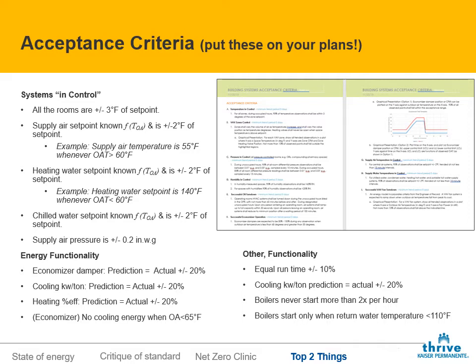And it turns out, what we've learned here, I guess, is that acceptance criteria fall into two categories. The first category of acceptance criteria is that you have your systems in control, right? All your rooms are plus or minus 3 degrees at the set point. Your supply air is plus or minus 2 on your supply air temperatures and your supply water temperatures, right? The pressures should all be within a margin of error that's within expectations. That's the first tier of acceptance criteria, is that your systems are in control.